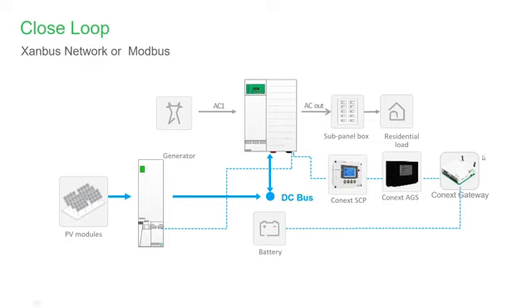With a closed loop integration, you see now I'm showing a communication cable that has gone daisy chain from my charge controller to the inverter, and then to the accessories, and then to the battery. So now this battery is in my network. And that network can be directly Xanbus network, which is what Discover does, or what many others do is Modbus with the gateway. What does this battery communicate?